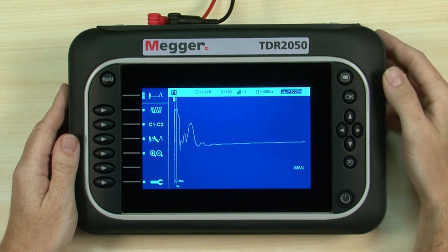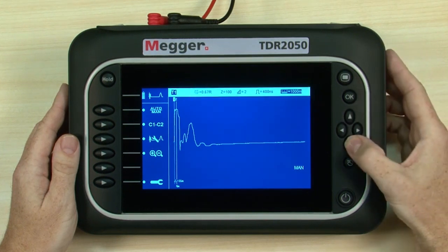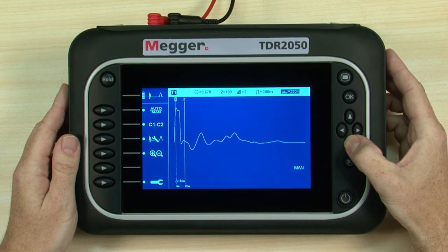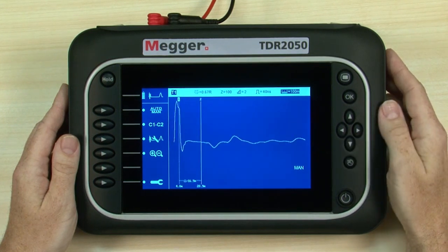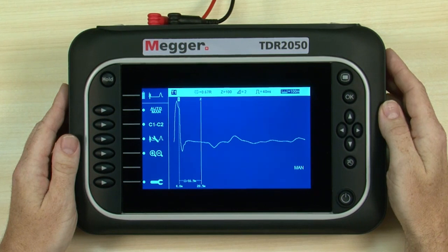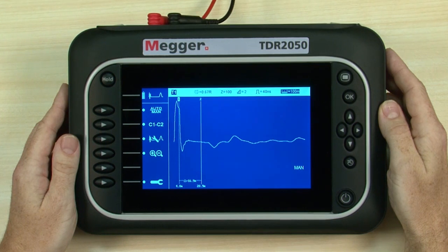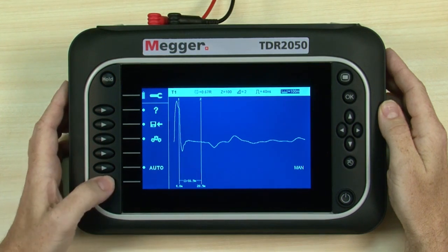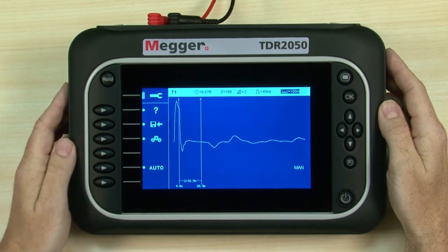Up and down buttons adjust the value for the selected parameter. We have around 100 metres of cable, so we need to decrease the range. The event is now more observable, but can be modified further if required by adjusting the other settings. To change other parameters, access the settings bar by pressing the soft key.